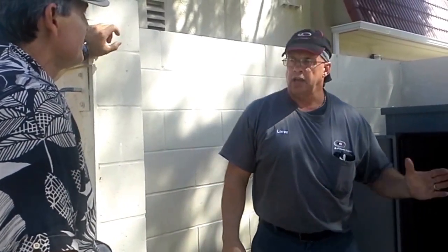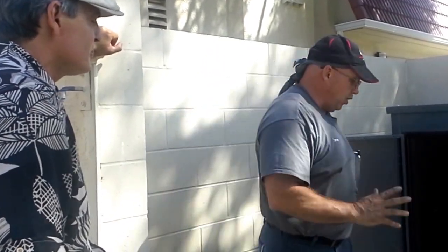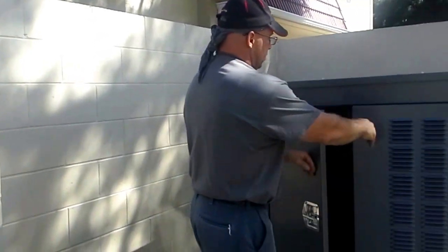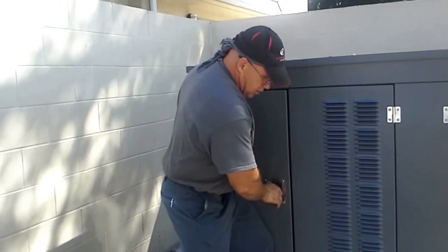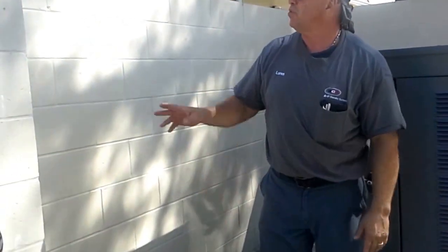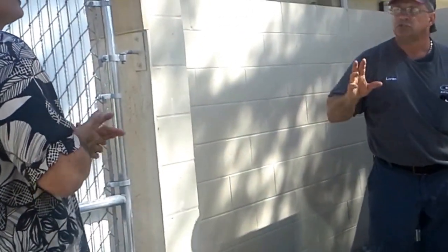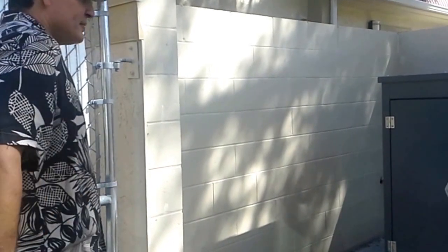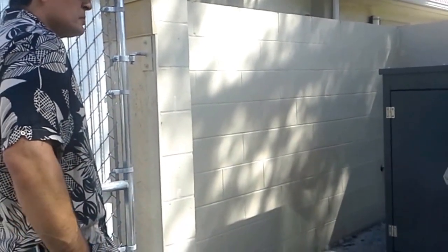With a load is always better for a generator than without a load. It's better reassurance for you. But once again, these are gas units. This will run at maximum temperature without a load, and I do want to reach maximum temperature. It's harder on diesels than it is on a gas. So with or without a load isn't that big of a deal here for a gas unit, but I still prefer with it because it's reassuring that it exercises and that the transfer switch is switching. So we'll come back to that one later. I don't know if you have to ask anybody else or anything.